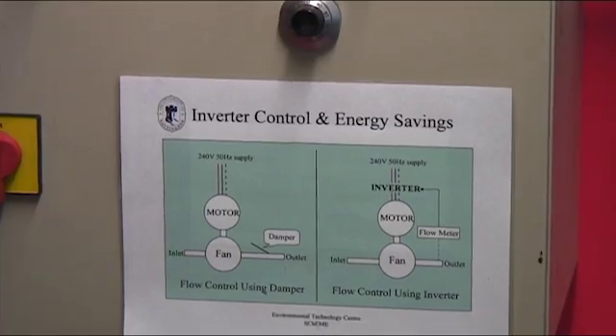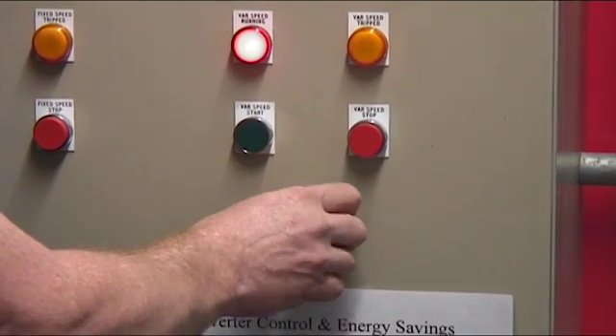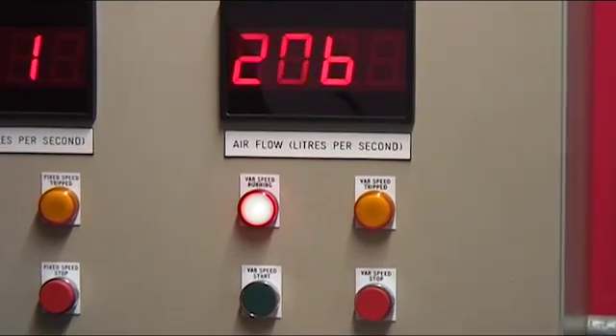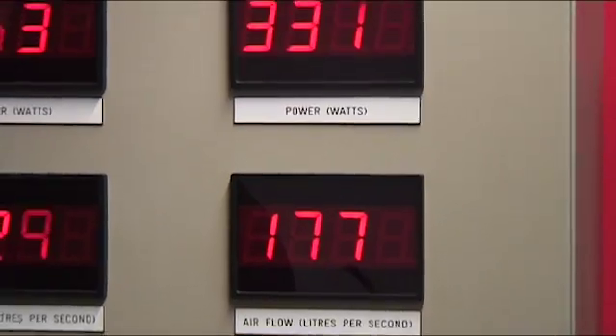What you can do if you install something called an inverter, which is an electrical device, you can actually turn down the speed of the motor on the pump, and therefore you're not pushing the hot water around as much. Because the more energy that is taken out of the heating system, the lower the return temperature. If the system isn't working as hard, so it's not putting as much heating out on the system, the return temperature will be hotter, therefore it doesn't have to do so much work. And you will accrue great energy savings in terms of the system operation due to less energy used to power the pump effectively. But if it's working 24/7, that's quite enormous.